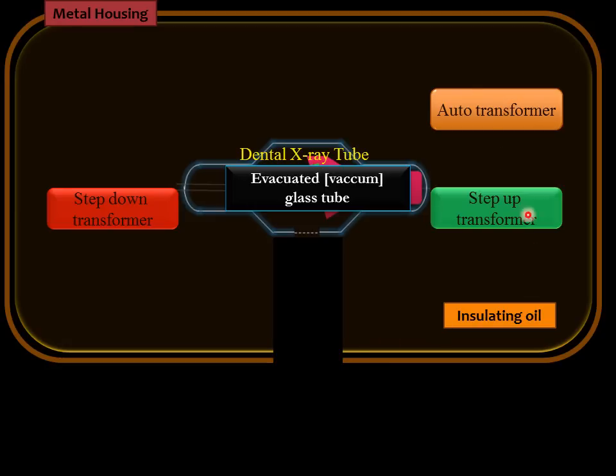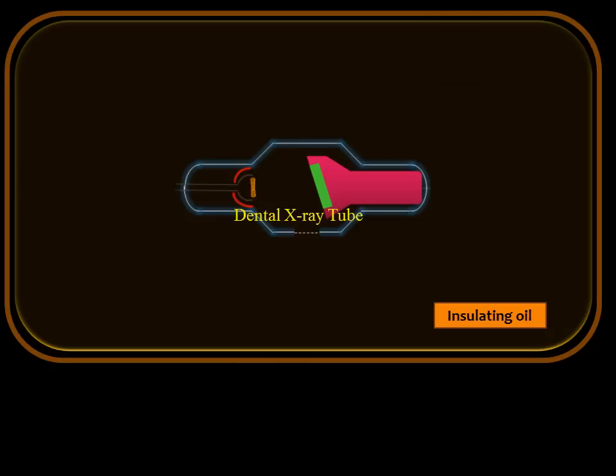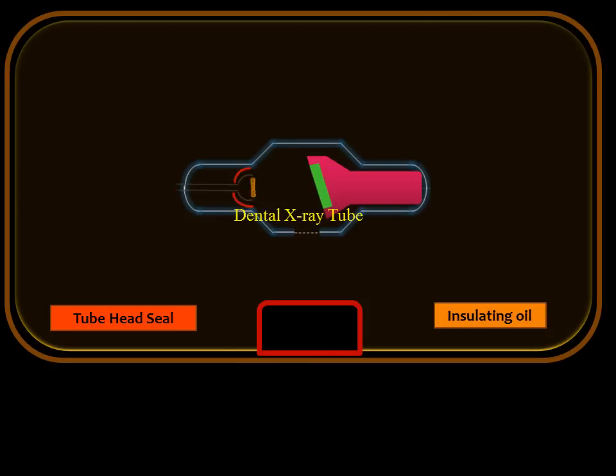The metal tube housing is completely covered except for a small part for permitting the x-rays produced to exit the x-ray tube head. This part has to be sealed so that there is no leakage of insulating oil. This is sealed with the help of a tube head seal, which allows the insulating oil not to leak from the x-ray tube.